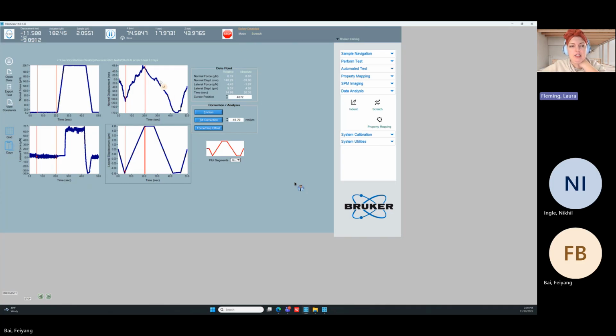So right now, because I have sample tilt, I cannot trust the change in normal displacement during my scratch, right? Any tilt is going to also be in that data. So if I want it to be accurate, I need to correct for that tilt. So we do so by selecting these 2 points with our cursors, and then only then can you hit tilt correction, because what that does is it takes the normal displacement between the 2 points and it says this should be 0, and it flattens it. So if you just hit tilt correction without choosing those points, you're changing the data strangely. It doesn't make sense. You have to pick where you measured the tilt. And we measured the tilt here because it has 0 normal force and we are scratching along the sample or tracing along the sample.